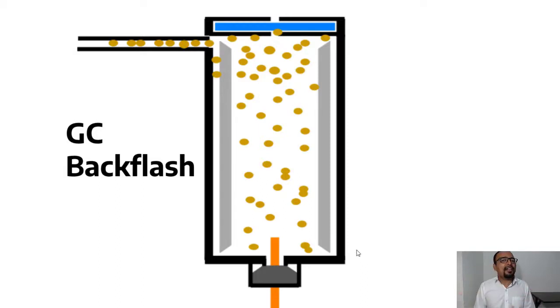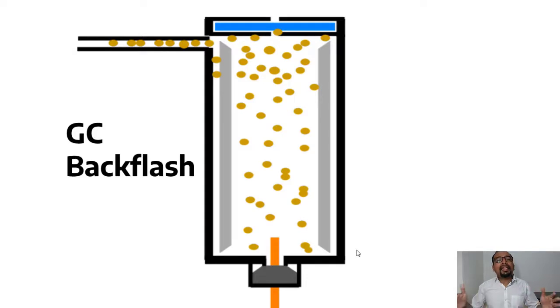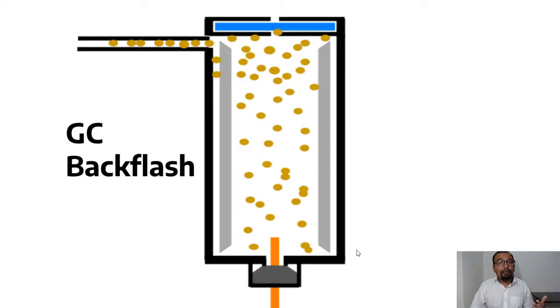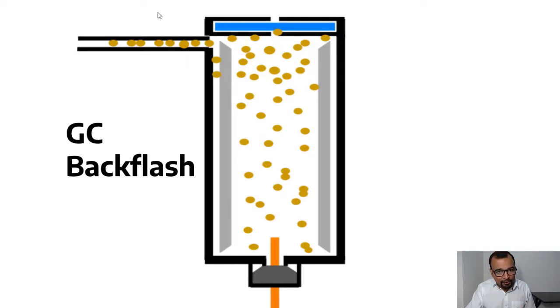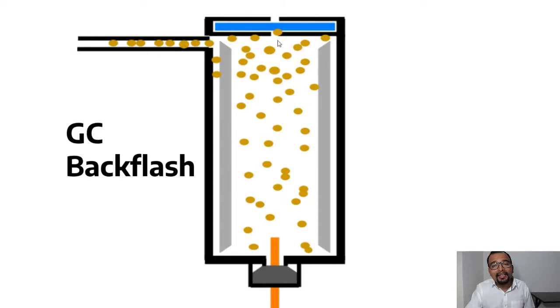When you make an injection into the injector port, your liquid sample undergoes vaporization. The vaporized form of the sample needs more space because the volume expands. If the available space is not enough to occupy the generated gas, the vaporized sample starts finding ways out — it can travel into the carrier gas inlet line or accumulate just below the injector septum. This is called the back flash.